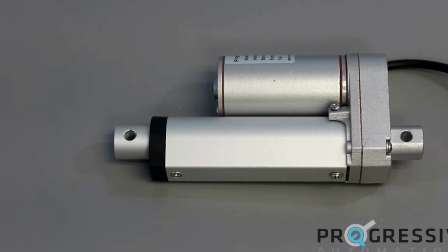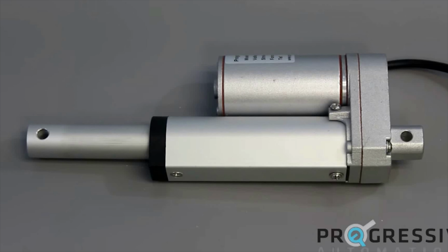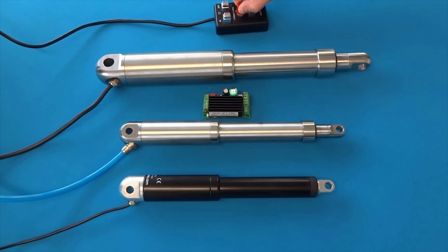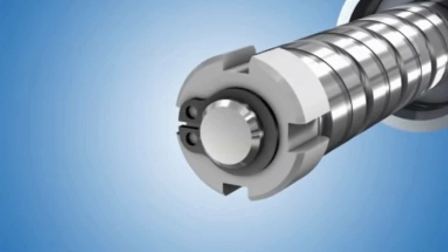Because linear motors cause lower friction losses than other devices, some linear motor products can last over 100 million cycles. Linear motors are divided into three basic categories: flat linear motors, classic U-channel linear motors, and tubular linear motors. Linear motor technology is the best solution in the context of a low load, up to 30 kg, because it provides the highest level of speed, control and accuracy.